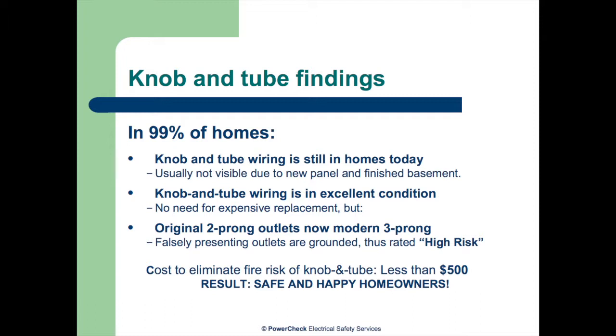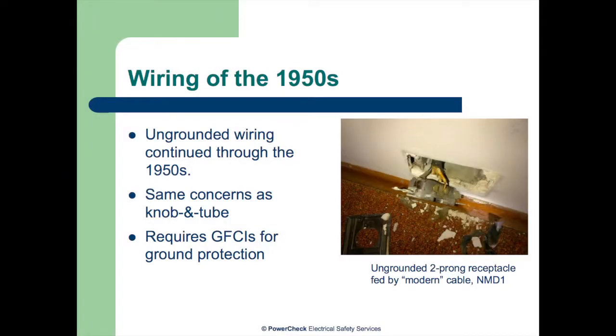But in 99% of the houses, the original two-prong outlets are now three-prong. Hence, the houses are rated high risk by PowerCheck. What's the fix? Hire an electrician to go through the house and change those outlets for GFCIs at a cost of less than $500 a house. Wiring of the 1950s: ungrounded outlets continued through the 1950s. They took the two wires of knob and tube and wrapped them together with a case. It had no ground. They were wired to two-prong receptacles, which have now been changed over to three-prong in most of the cases. Again, in those houses, the solution is GFIs.